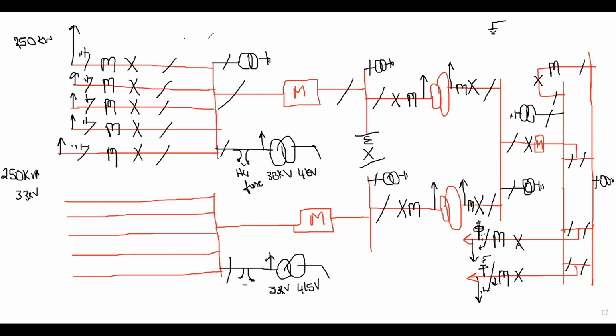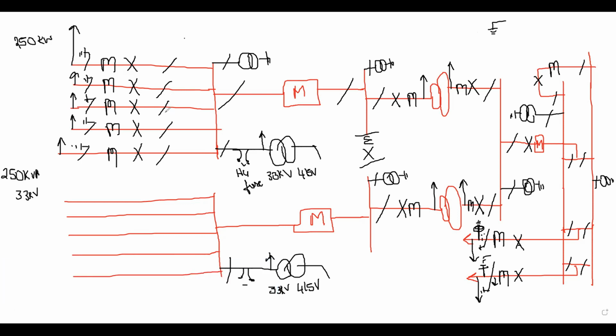So the next thing is I have to give a designation to each and every equipment, because when I am sitting at the commissioning of the substation, in front of the computer, and I want to operate the breaker or isolator to take it into maintenance tomorrow, how shall I know which one to open? So I have to name this. By just clicking on the isolator open, it has to open. So how can I know this isolator? I have to name this isolator, and each and every equipment in the substation has to be named.